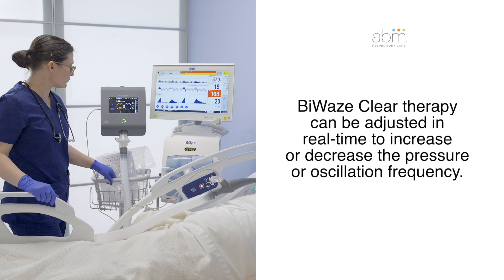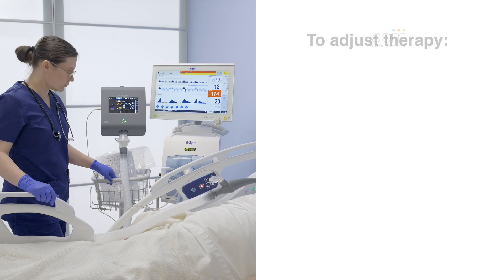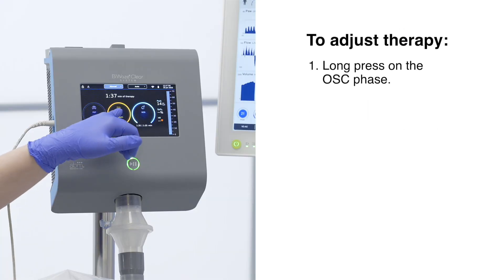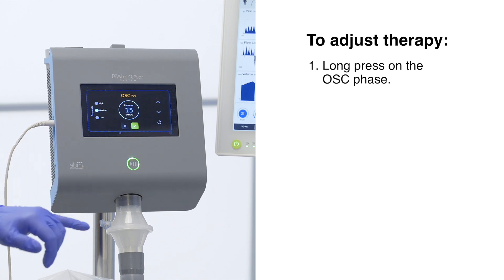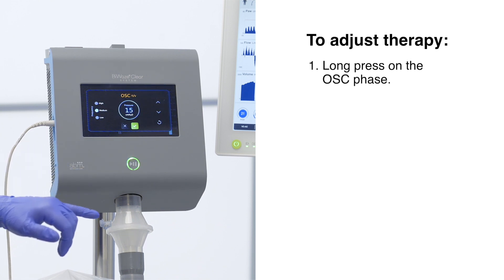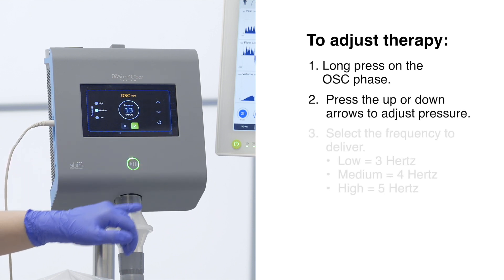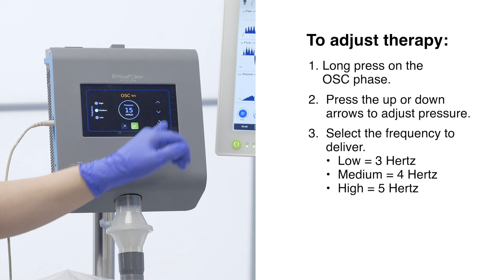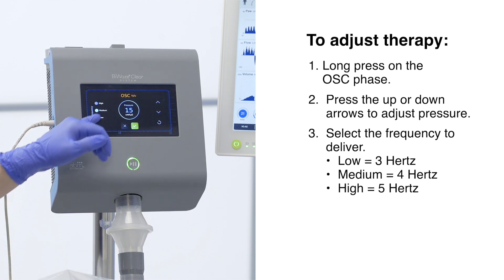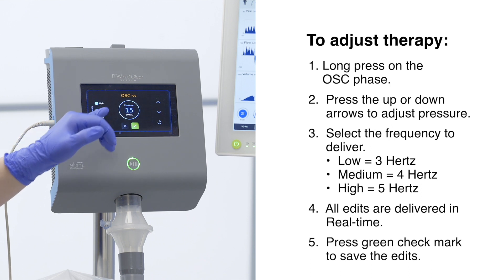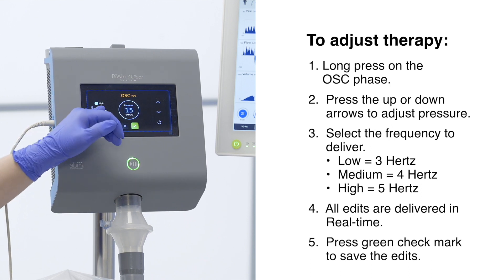BiWaze Clear therapy can be adjusted in real-time to increase or decrease the pressure or oscillation frequency. To adjust the therapy, perform a long press on the OSC phase circle. A window will open where the pressure can be increased or decreased in real-time by pressing the up or down arrows. Frequency can be adjusted by selecting low, medium, or high. Press the green check mark to save the therapy changes and return to the Manual Mode Therapy screen.